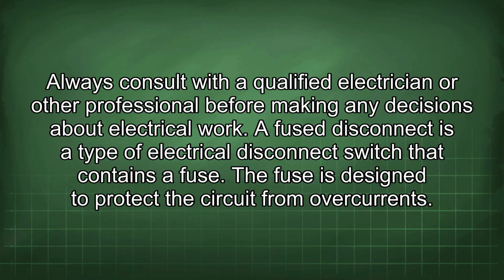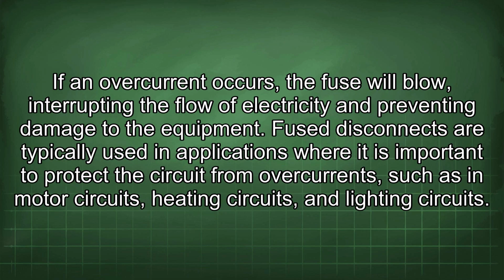A fuse disconnect is a type of electrical disconnect switch that contains a fuse. The fuse is designed to protect the circuit from overcurrents. If an overcurrent occurs, the fuse will blow, interrupting the flow of electricity and preventing damage to the equipment. Fuse disconnects are typically used in applications where it is important to protect the circuit from overcurrents, such as in motor circuits, heating circuits, and lighting circuits.